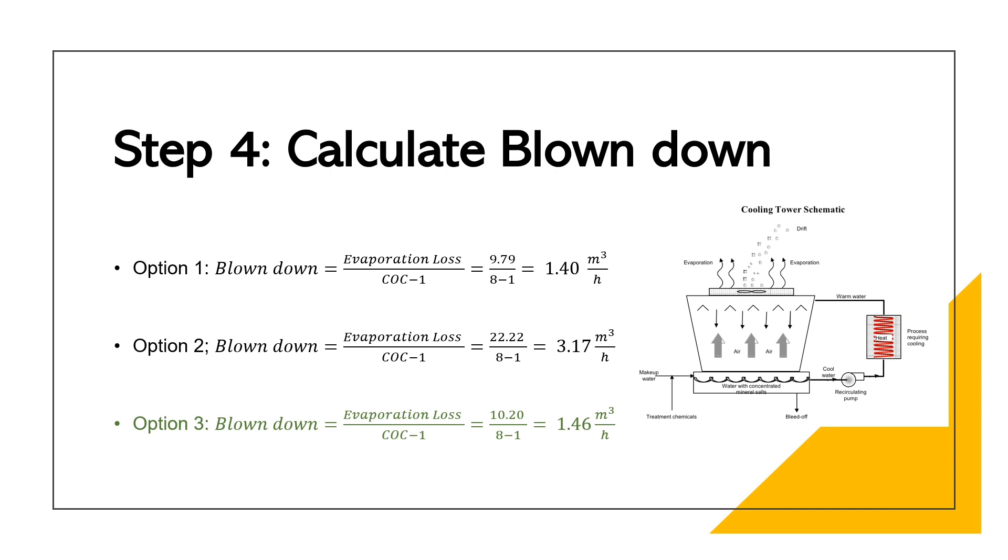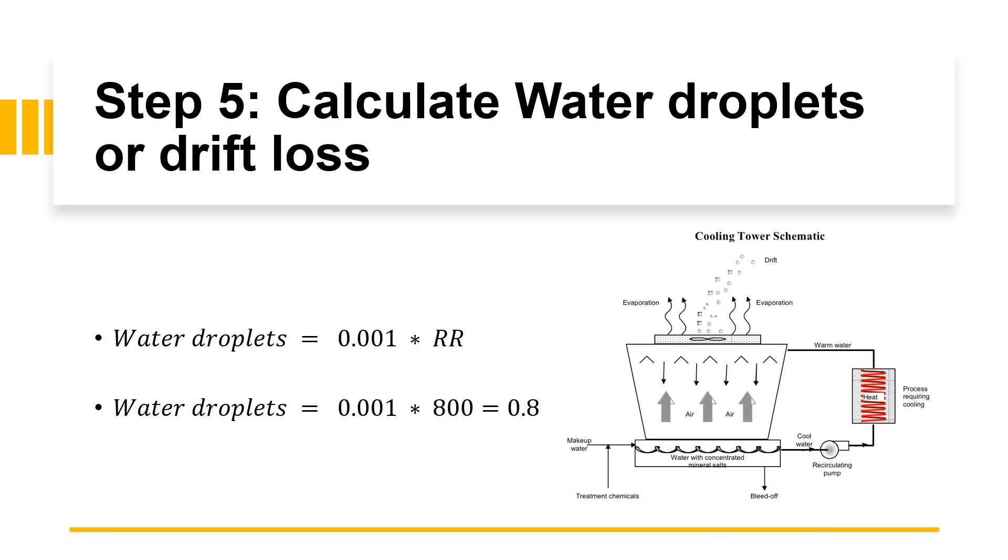Now for the blow down. Blow down is the relationship between evaporation loss and CoC minus one. Now let's assume a cycle of concentration of eight. And for each option, let's calculate the evaporation loss. Remember option one evaporation loss we got 9.79, hence we punch everything to calculator and you get a blow down of 1.40. Do the same thing for all three options. Again we are going to assume the third evaporation loss was the accurate equation here, hence let's move forward with the blow down option three as well.